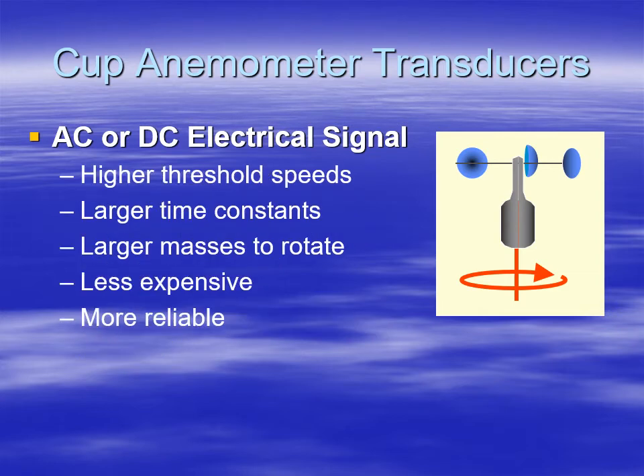The problem with this type of transducer, of course, is that you have magnets at the end of the shaft. Magnets are more massive. You have more mass to rotate. So, of course, you have larger time constants or distance constants, higher threshold speeds, and this is a little bit more expensive. However, this is a very reliable technology, so they tend to survive out in the elements.